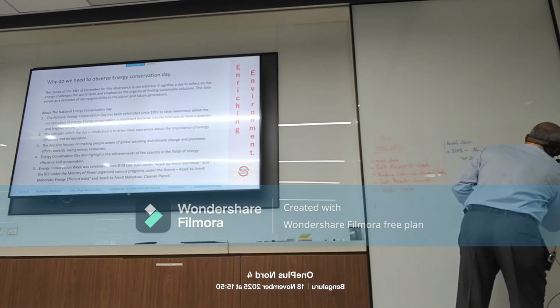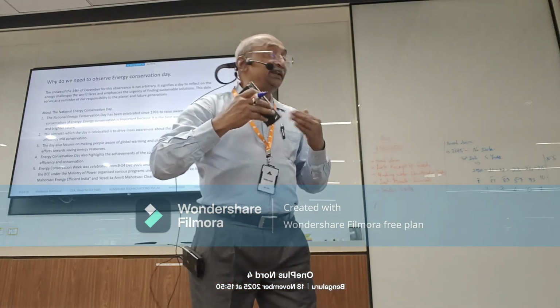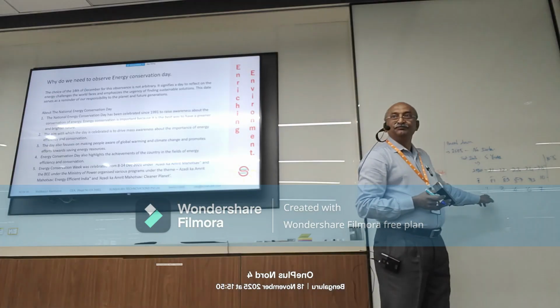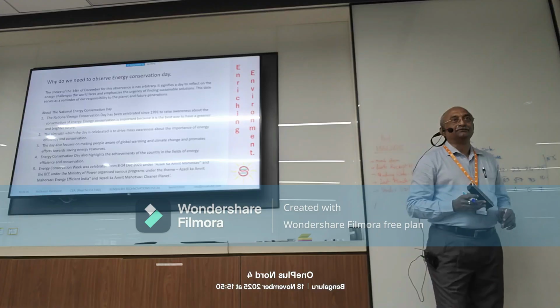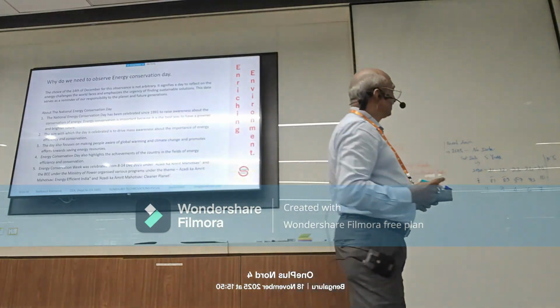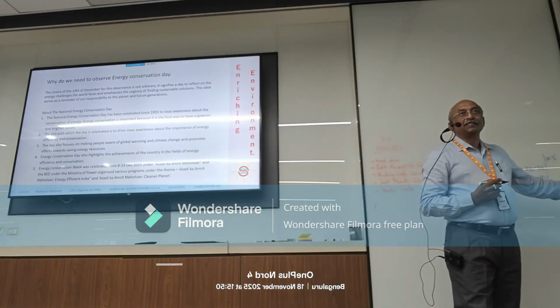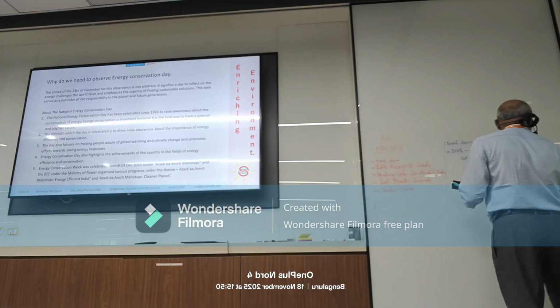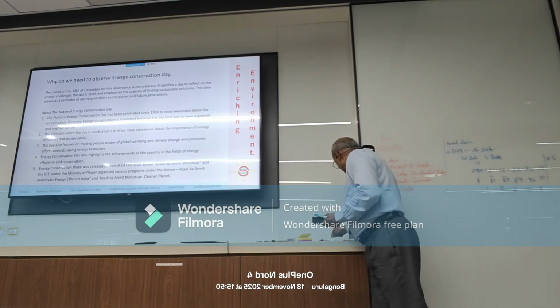Point 4, and this is 0.6, right? This is 0.7. Now, the increase in moisture content in the transformer oil. Initially, when you took it, it was 8 units; first year 0.1, second year 0.2, third year 0.3, 0.4, 0.6, and 0.7. Right? Now, what is the cutoff value, I mean the safety value? 10.5. So that means if the trend continues, it is for sure that you are getting into the red zone.